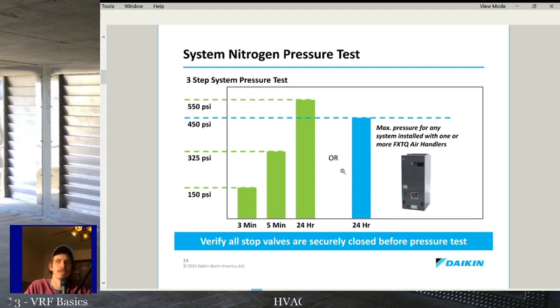Systems have some leakage no matter what you do. There's leakage through the copper pipe, alright? But there's also leakage mainly through every braze joint you have, every flare connection you have. Anywhere where there's a weak spot, you're going to have more leakage than you would otherwise. And the only way to minimize that leakage is to do a pressure test and to catch as many of the larger leak points as possible. Hopefully there are no large leak points, but there may be, so you need to find whatever you got. So you want to do it on every system.